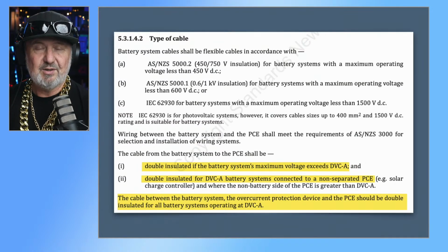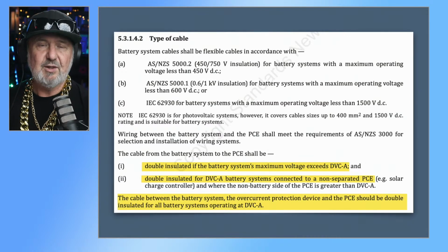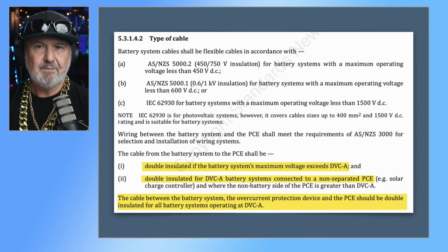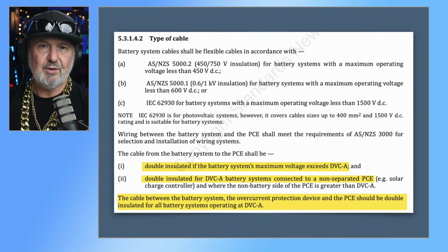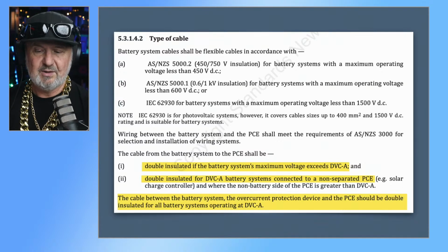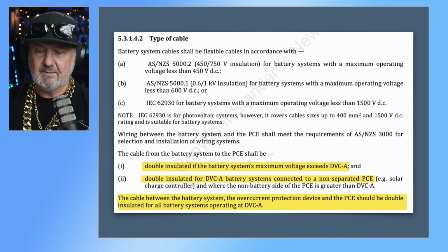And it's actually to do with safety because certainly with inverters that are non-galvanically isolated, which is basically all grid tie inverters these days, they are transformerless, you can actually have earth faults through either pathway. So you can have earth faults through the positive or through the negative conductor. So you need to be able to isolate both of them. So it's actually a higher level of safety.